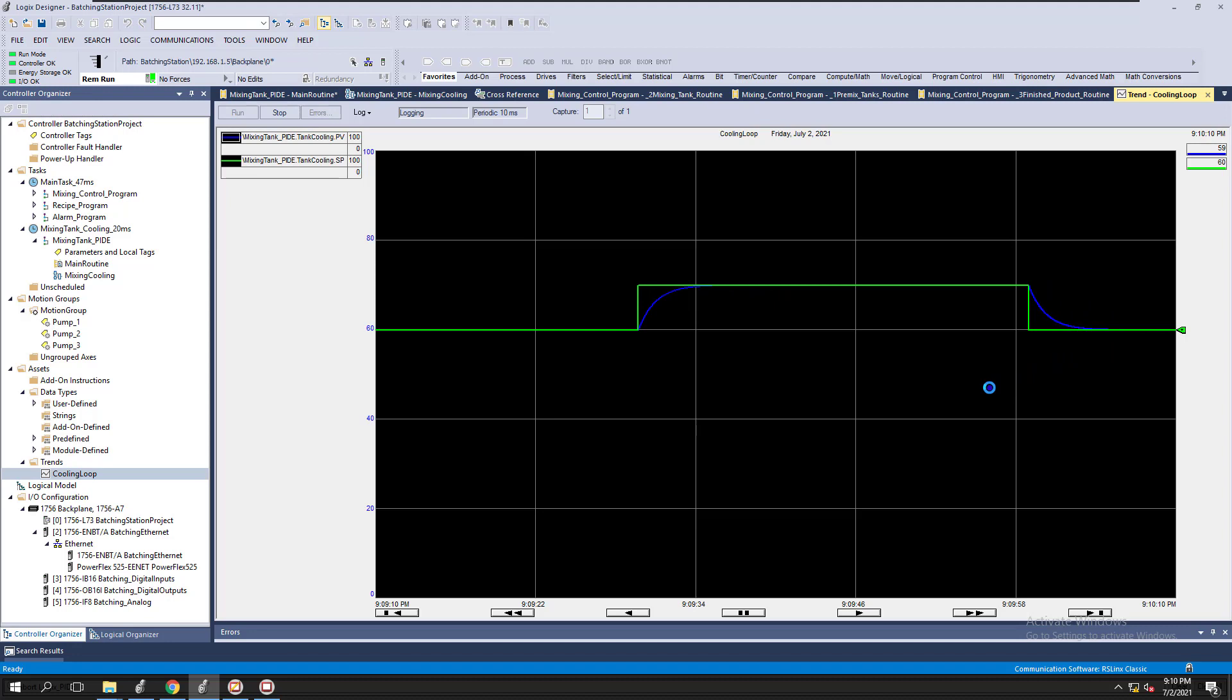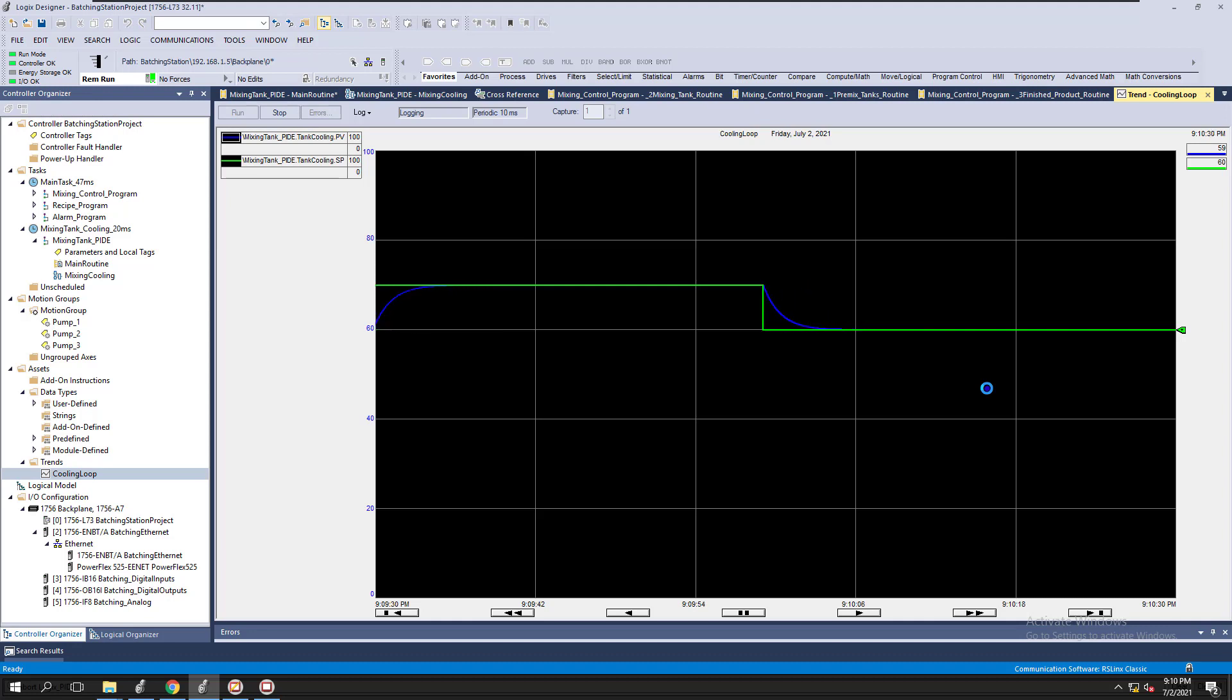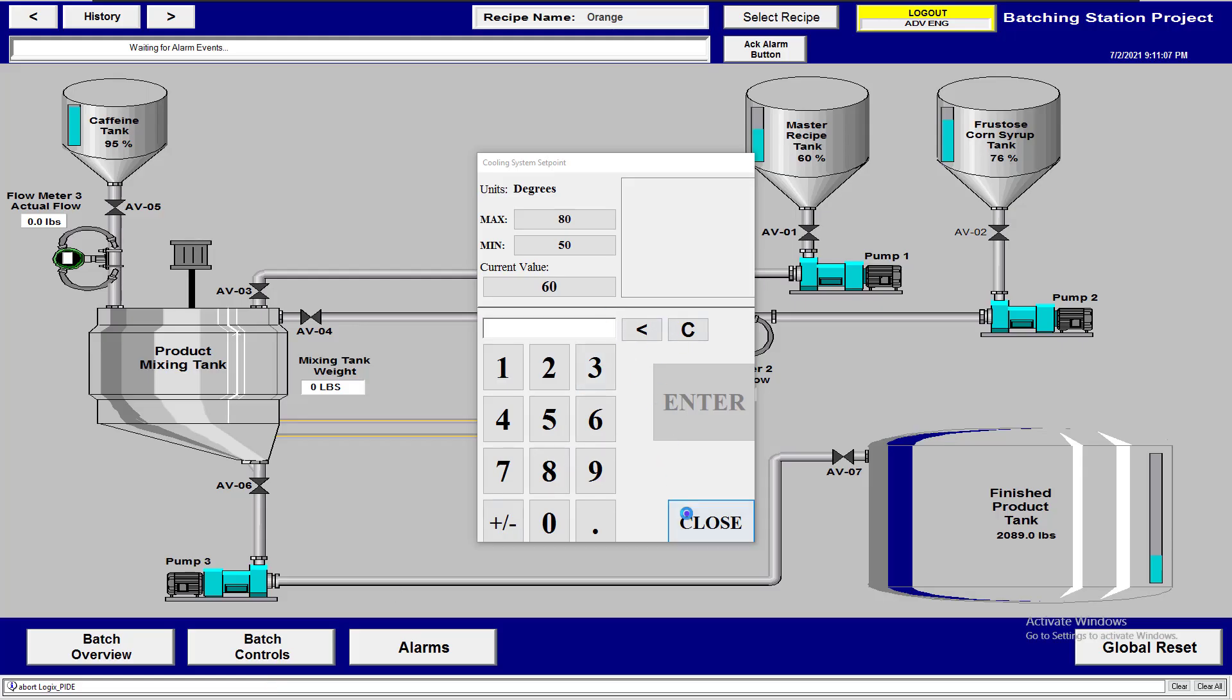And again, after you tune everything and you have everything auto tune, like I said, you're not going to come back and tune a PID just that, you know, after it's already been set up. Generally speaking, you're only going to tune or change tuning at all on a PID is when you have like a process change, not when you have like something's just been running for years and you have, then all of a sudden it's not working right. You need to start looking at that point in time. You need to start looking at the field end of things and see what's wrong in the field, like in a medical mechanical device or maybe something in the process has changed that it's kind of unforeseen, you know, could be something stuck, could be something not working properly. Again, you're not going to have to change the tuning of a PID just randomly out of the blue, right? So that's why we say it's generally a constant.